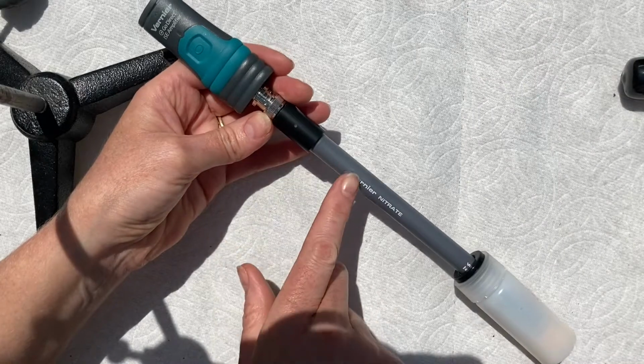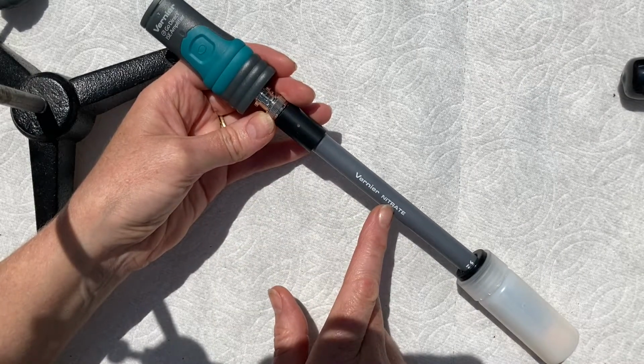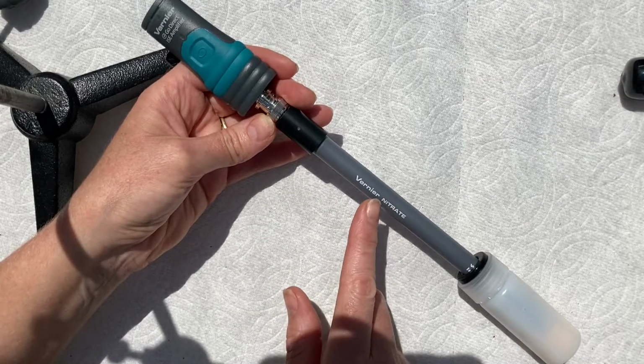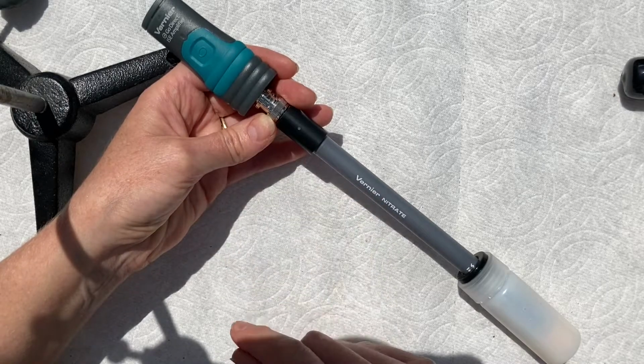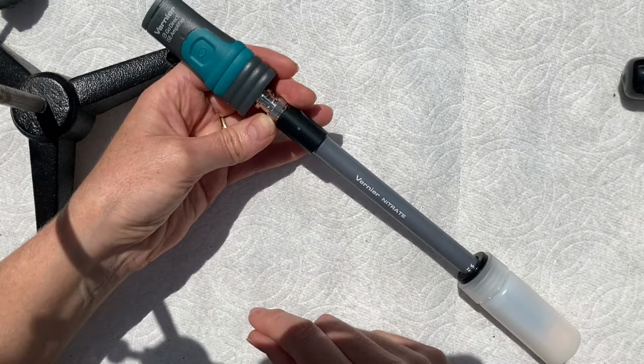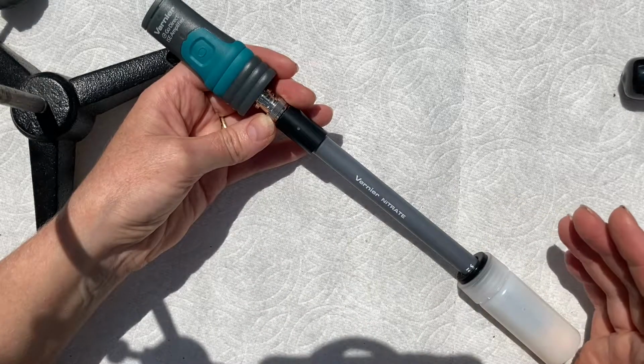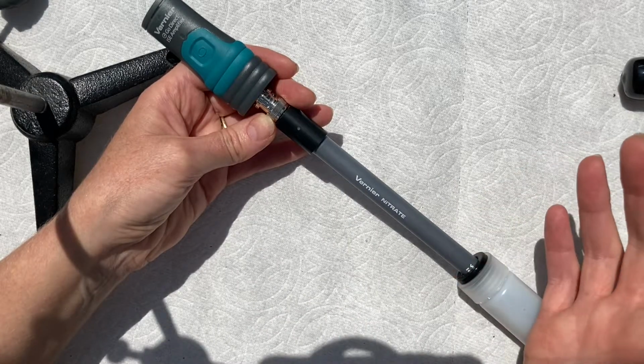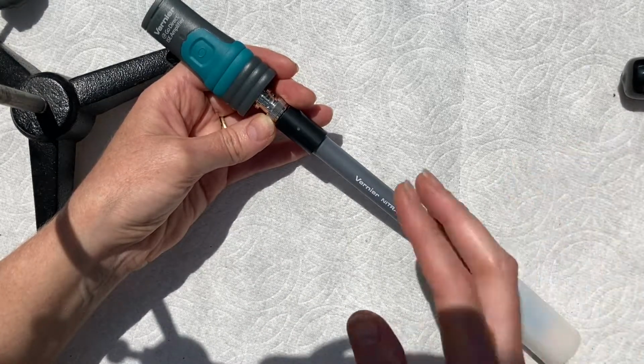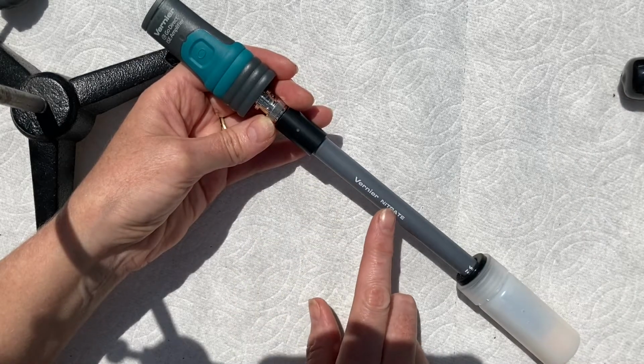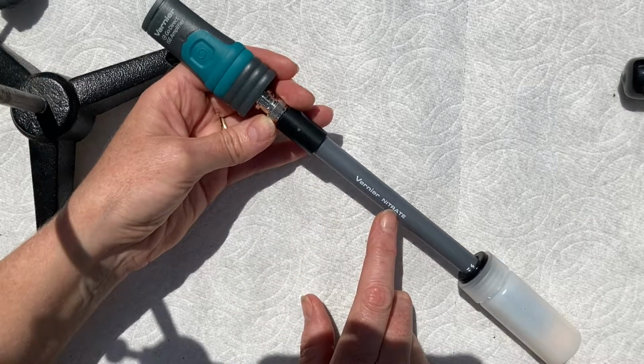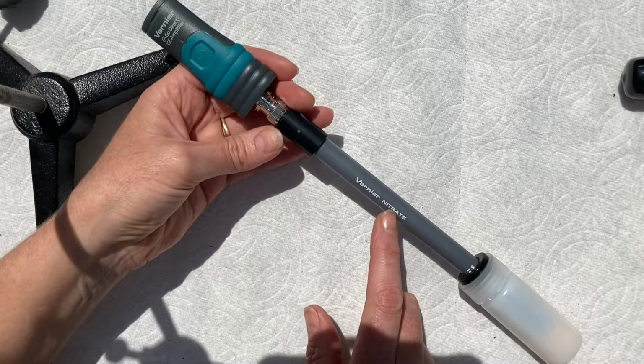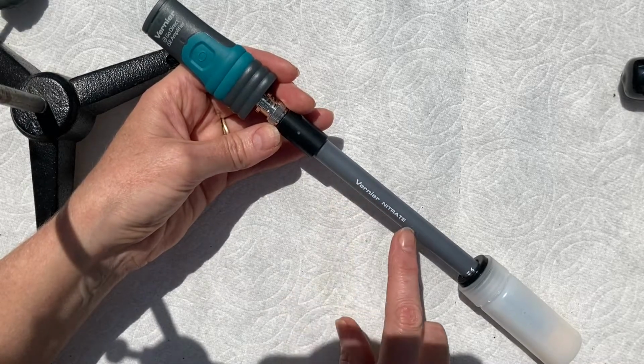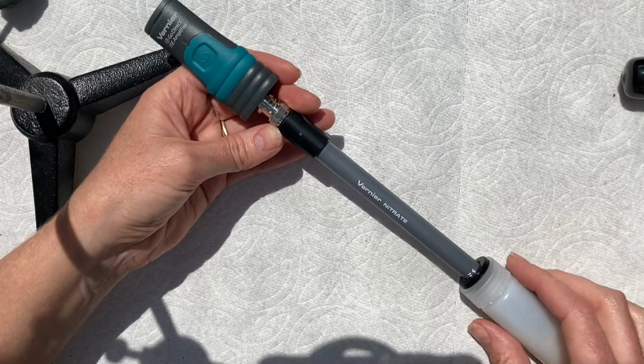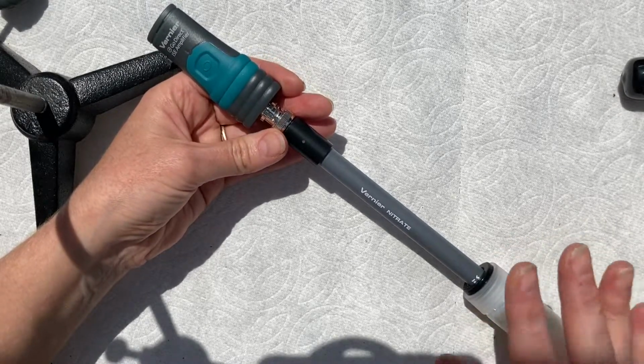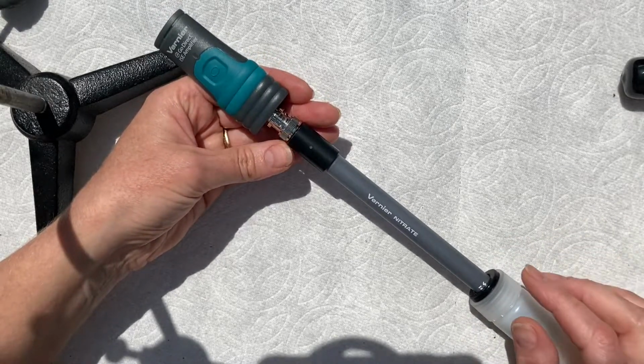But last year I got one of these from Vernier to review, and I was much impressed because it kept its calibration all day. So it still needs to be calibrated when you do any kind of water quality testing, and it's been a week or so. And actually, I tested it a week later and it had still held its calibration. So it might last longer than a week for calibration. It might be 2 or 3 weeks for calibration now, which again is a big improvement over the old sensors for nitrates.